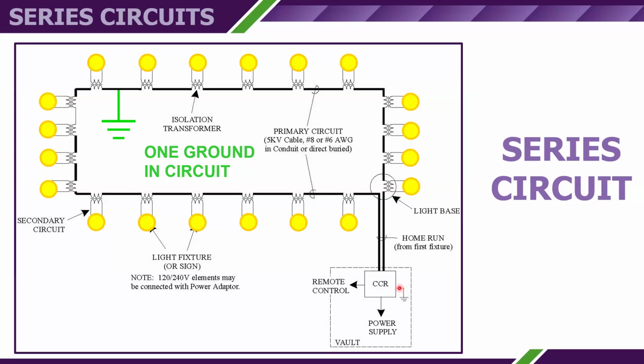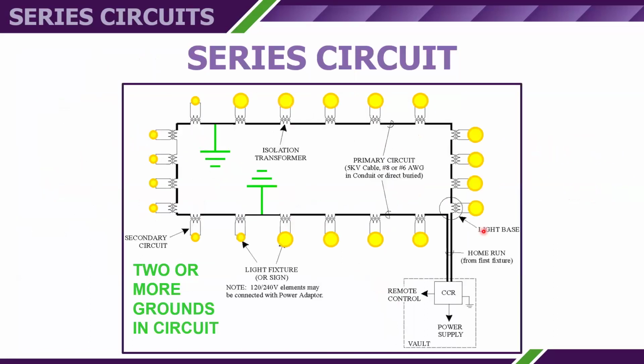Remember earlier I mentioned that all the current that leaves the constant current regulator has to go back to the constant current regulator. Going to ground is not one of its options because it has no way to get from this ground back to the regulator. So all the current is going to continue in the copper wiring, going back to the regulator. It leaves the regulator, has to get back to the regulator. With a single ground, there's no path for current to flow.